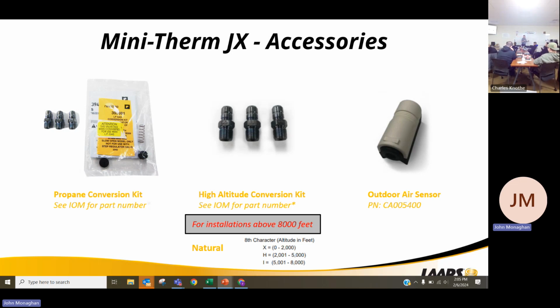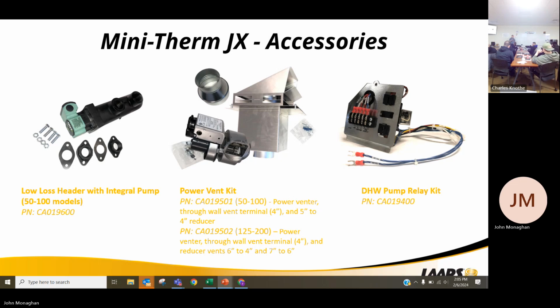High altitude, we're not high altitude here. We don't have to worry about it. And there is an optional outdoor air sensor, and we can get into that. You are able to do outdoor reset with this product, or you can use its factory thermal targeting, and we'll get into what they do as well. Other accessories with it, all of your larger models are going to come standard with that little header on there. The smaller models, 50, 70 to 100, it's optional.